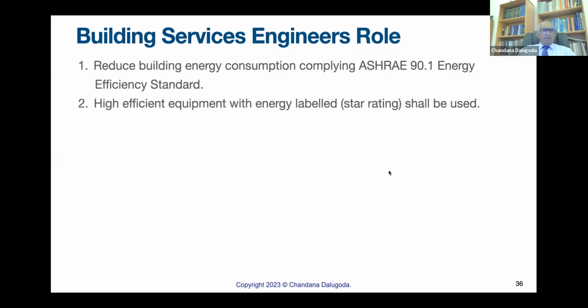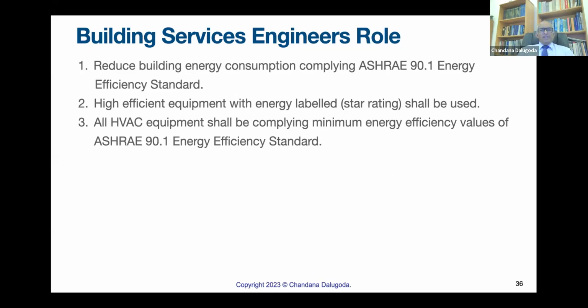Simple example. Air conditioners will have to comply. If it is VRF or DX systems, then the energy efficiency ratio should be 11.3 and above. You can't use 9 EER. In Sri Lanka, most of the equipment we find brought here is 9 EER or maximum 10. If it is chillers, that is COP, we'll discuss that, or kilowatt per ton. All HVAC equipment shall comply with the minimum energy standard values from 90.1. That we'll discuss separately.